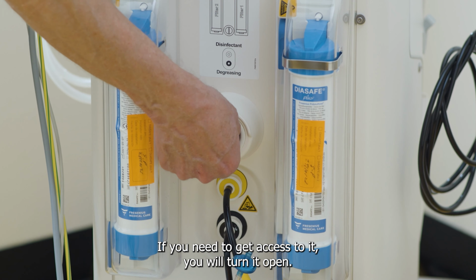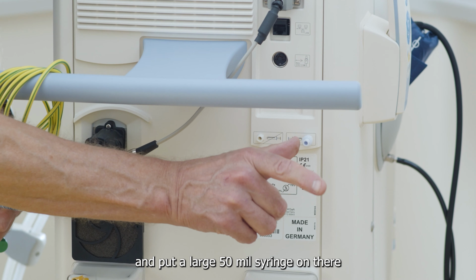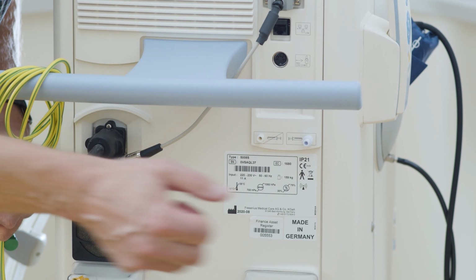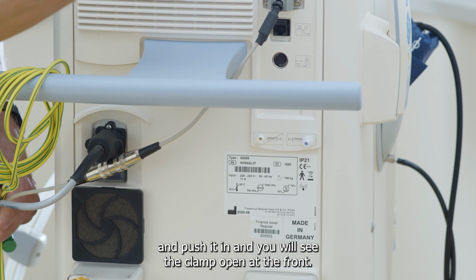However, to do that, you need to put this white connector there, which is a non-return valve, onto that port there, and put a large 50ml syringe on there and push it in, and you will see the clamp opening at the front. It might take more than one push on the syringe. You may have to disconnect the syringe from that white connector and give a second push on it. When not in use, that non-return valve needs to sit on that holder there to that side.